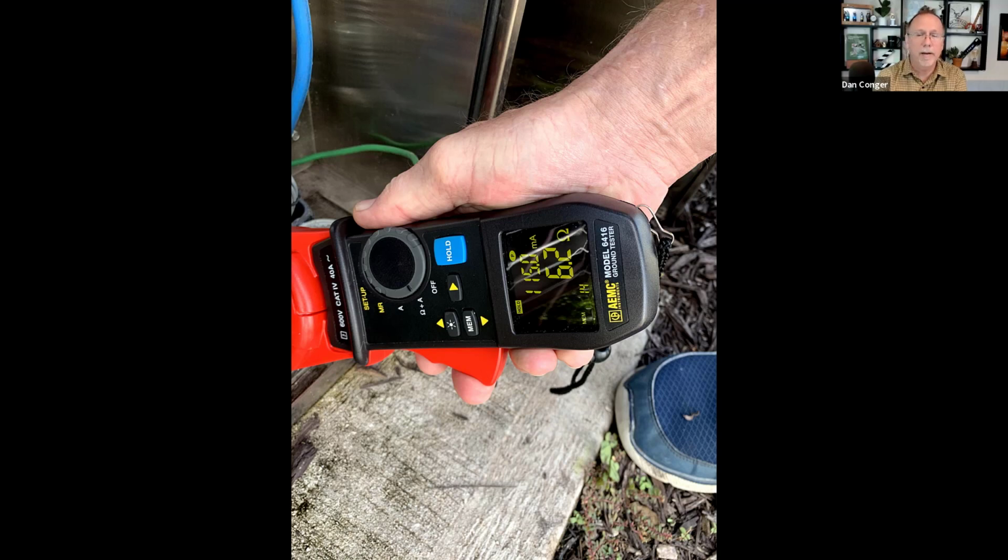And so that's the resistance we're looking for. Just having a ground point connected to the wire path is great. That's part of the spec. The other half of the spec is having low resistance at that ground point. So Idral here had a clamp-on meter, and a clamp-on meter is only used for testing at the controller, so this would be the pedestal or the cabinet ground. Here it looks like you had 6.2 ohms of resistance. The spec is 25 ohms or less. We recognize that 10 ohms is even better. So this definitely meets both of those specifications as far as low resistance.